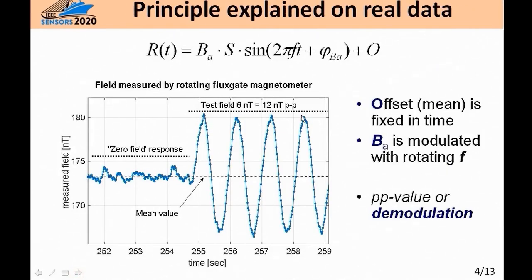Let's explain the principle using real data acquired during Fluxgate sensor rotation in the horizontal plane. This is the basic equation showing how the field gets modulated: the ambient field BA, the rotational frequency, the sensor sensitivity, and the offset. The only time-dependent component is the one related to the ambient field - the sensor offset is stable in time.